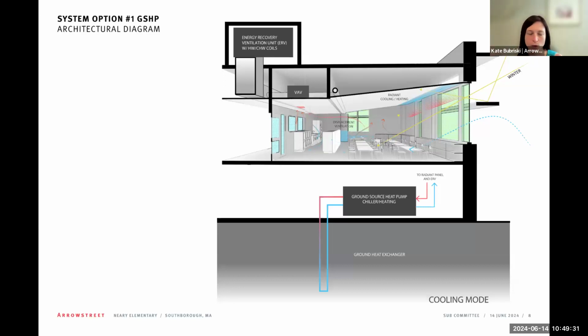If you decide to do the ground source system, they'll do a desktop review and figure out what projects have been done more locally. They'll look at the geology, they'll look at the borings, they'll make a guess. And then at some point you do the test well, which means you do 1 or 2 wells that can be used in the real building once you get to full construction, but those are to double check the thermal conductivity that you're receiving on site. So essentially the well's just serving as a conduit for the pipe going down and the pipe coming back up. Where the air source heat pump is relying on your air instead of your rock and earth as your heat transfer. Okay. I'll have more dummy questions.